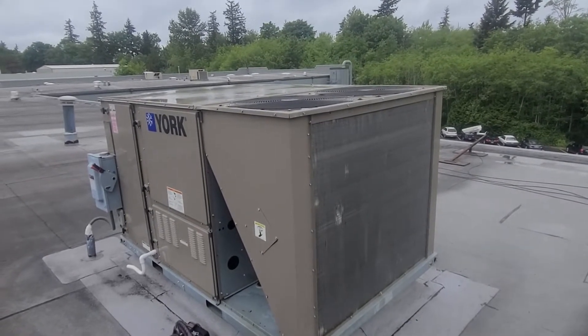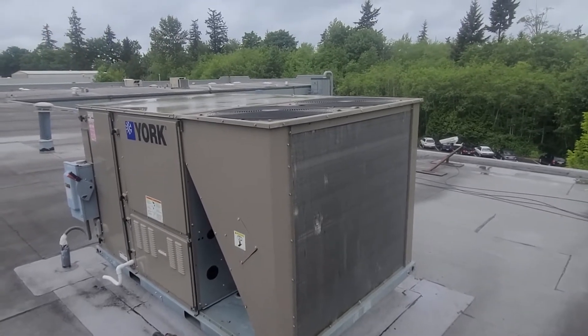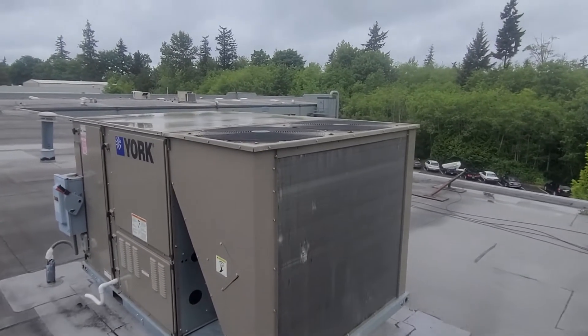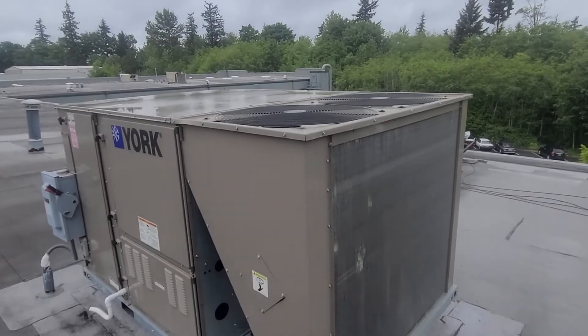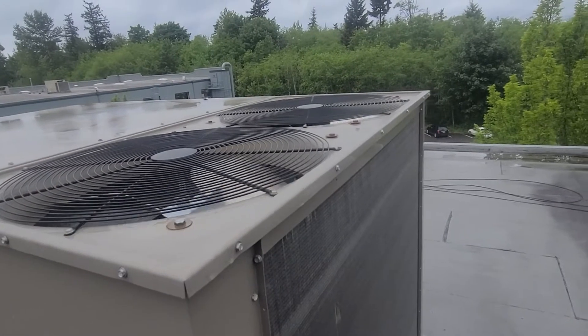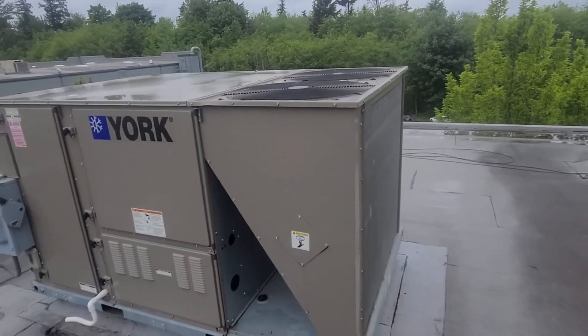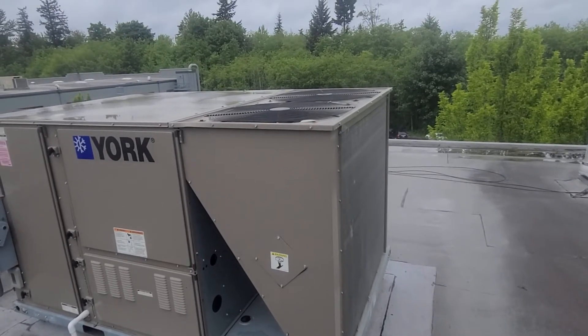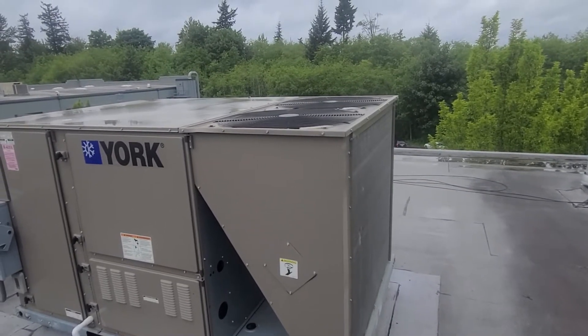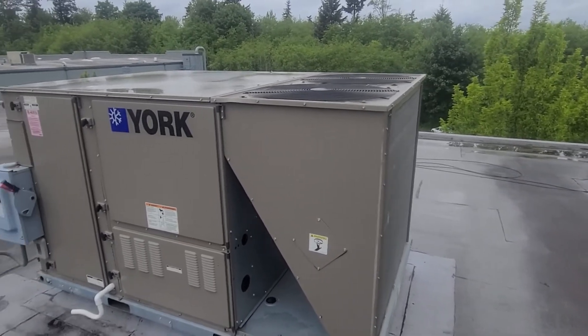With that being said, I am definitely going to write up new condenser motor fan blades for both of these, just because they're shaking so horribly. I'm probably also going to end up tightening up all these bolts, because with all this extra shaking, I know that's put a lot of wear and tear on anything fastening them down — I'm sure things have rattled a little loose.